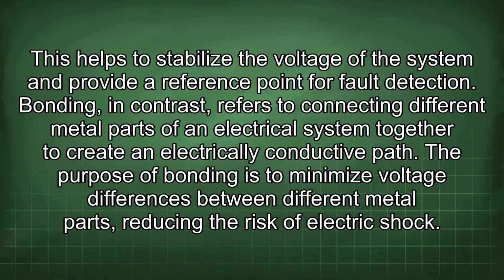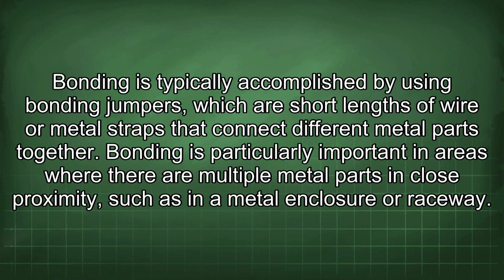Bonding, in contrast, refers to connecting different metal parts of an electrical system together to create an electrically conductive path. The purpose of bonding is to minimize voltage differences between different metal parts, reducing the risk of electric shock. Bonding is typically accomplished by using bonding jumpers, which are short lengths of wire or metal straps that connect different metal parts together. Bonding is particularly important in areas where there are multiple metal parts in close proximity, such as in a metal enclosure or raceway.